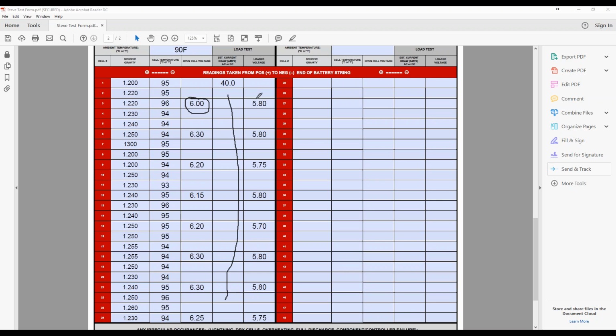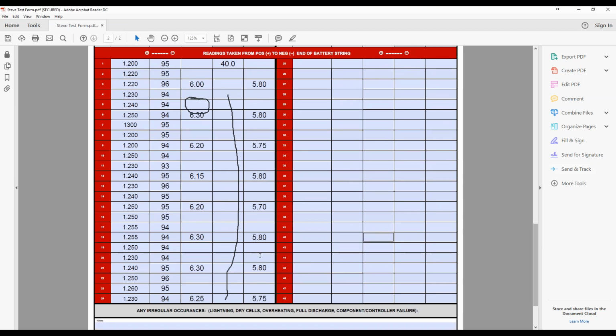Then you write down what the voltages are loaded. You could do this over time, or you could do it one time. But a lot of times what you'll see with a battery bank that's got, say, a good specific gravity but the battery's in the process of failing, you'll see something like 5.8, 5.8, 4.2, 5.8, 5.8 - so you'll see differences in those cell voltages.